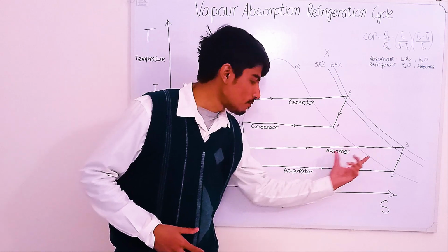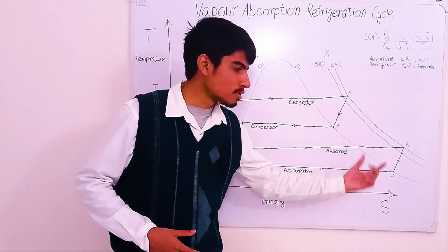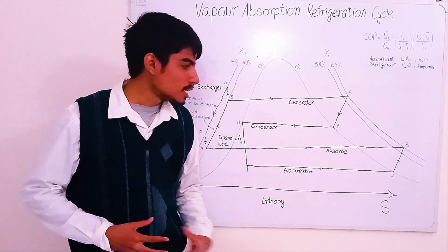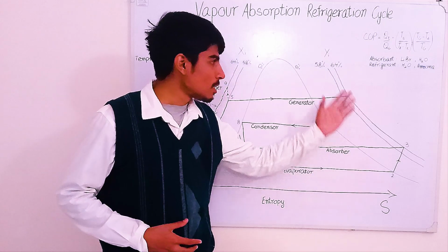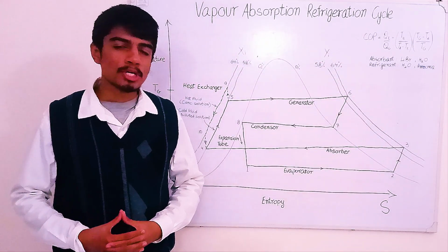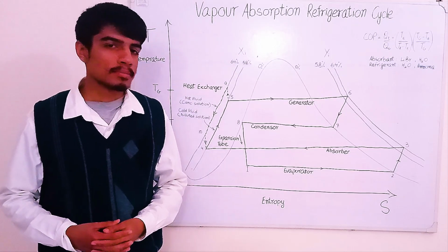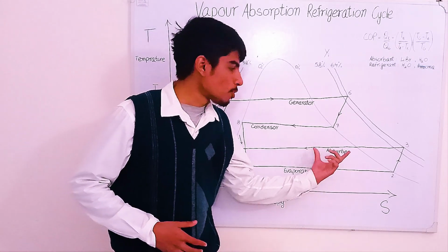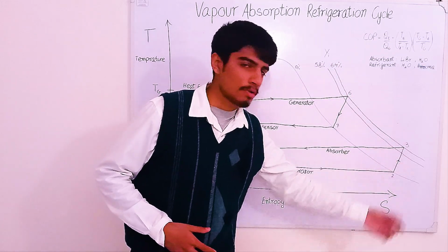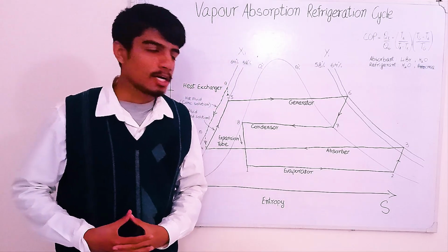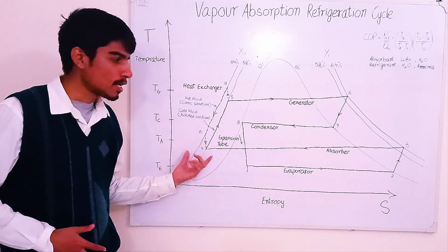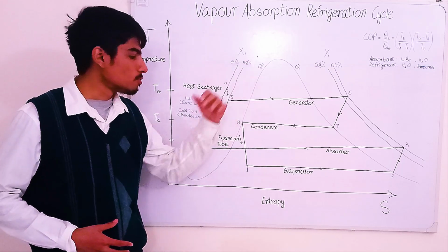The absorber is separated from the evaporator using baffles. It is a shell and tube type heat exchanger. In the shell of the absorber, showering of strong solution is performed, while in the tubes, cooling water is circulated. In the shell of the absorber, the strong solution absorbs the incoming vapors of refrigerant, due to which its concentration starts decreasing, and at the outlet it becomes a weak solution.